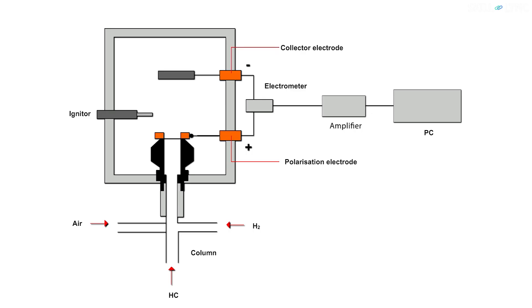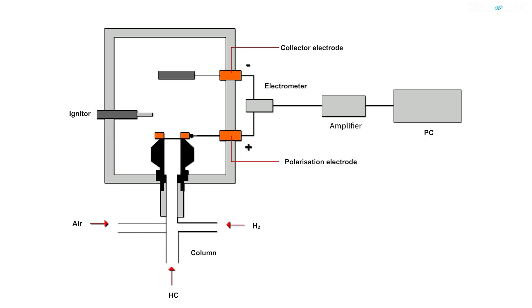The ion-collector assembly consists of two electrodes to create a potential difference. The positive electrode, also called the polarization electrode, is placed nearer to the nozzle of the inlet gases, and the negative electrode, also called the collector electrode, is placed at the top of the flame. These electrodes are connected to an electrometer which in turn is connected with an amplifier. The amplifier sends the signal to the computer display.